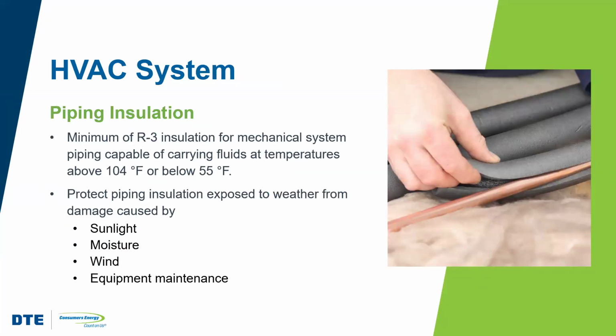And any HVAC piping in a good design will be covered with insulation, particularly if it's conveying fluids that are at elevated temperatures of 104 degrees or higher, or if it's at temperatures that are depressed at less than 55 degrees. The R value for that insulation, the minimum requirement, is R3.